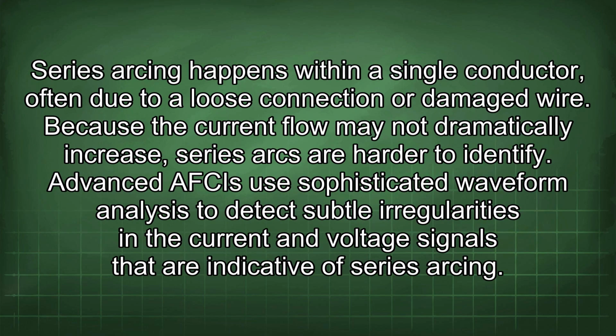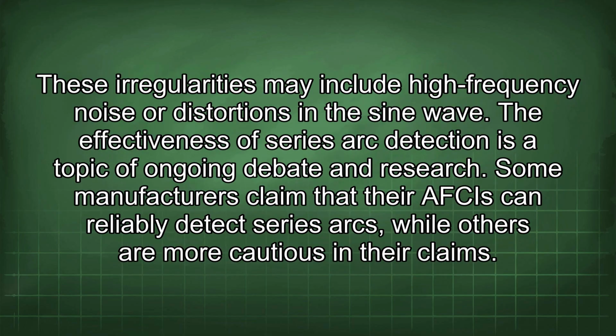Series arcing happens within a single conductor, often due to a loose connection or damaged wire. Because the current flow may not dramatically increase, series arcs are harder to identify. Advanced AFCIs use sophisticated waveform analysis to detect subtle irregularities in the current and voltage signals that are indicative of series arcing. These irregularities may include high-frequency noise or distortions in the sine wave.